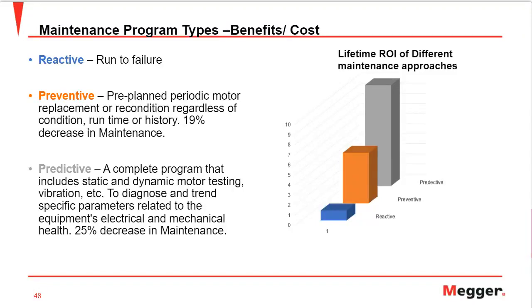And predictive testing is what we are looking at, which gives us the maximum ROI. It's almost 10 times what reactive could give, and almost twice what a preventive maintenance program could give. Also, predictive maintenance decreases total maintenance by 25%, while preventive does it by 19%. And reactive, of course, we let the motor run until it fails. So the whole point of surge testing and DC high potential testing is that these tests are conducted at a voltage higher than the rated voltage, but as we've seen, in real scenarios where a motor has to run every day in operation, it faces higher voltages and higher spikes than our test voltage for that rated voltage.